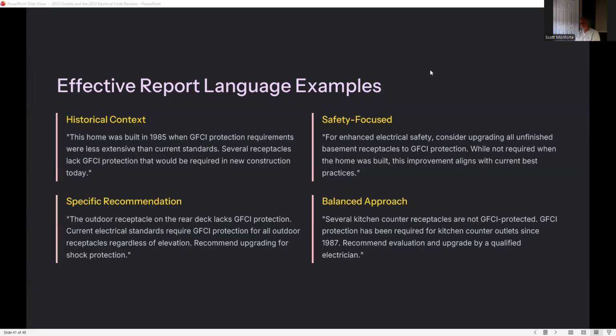Balanced approach: several kitchen counter receptacles were not GFCI protected. GFCI protection has been required for kitchen countertop outlets since 1987. Recommend evaluation and upgrade by a qualified electrician. Also, the islands in a kitchen need to have that protection and to have an outlet.